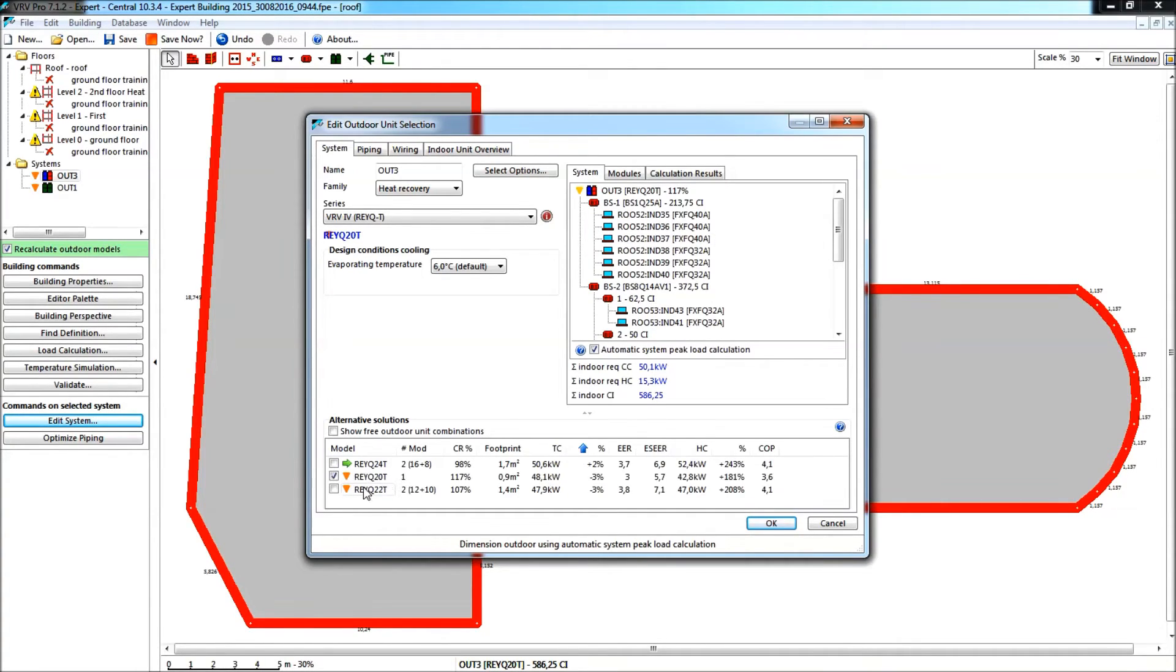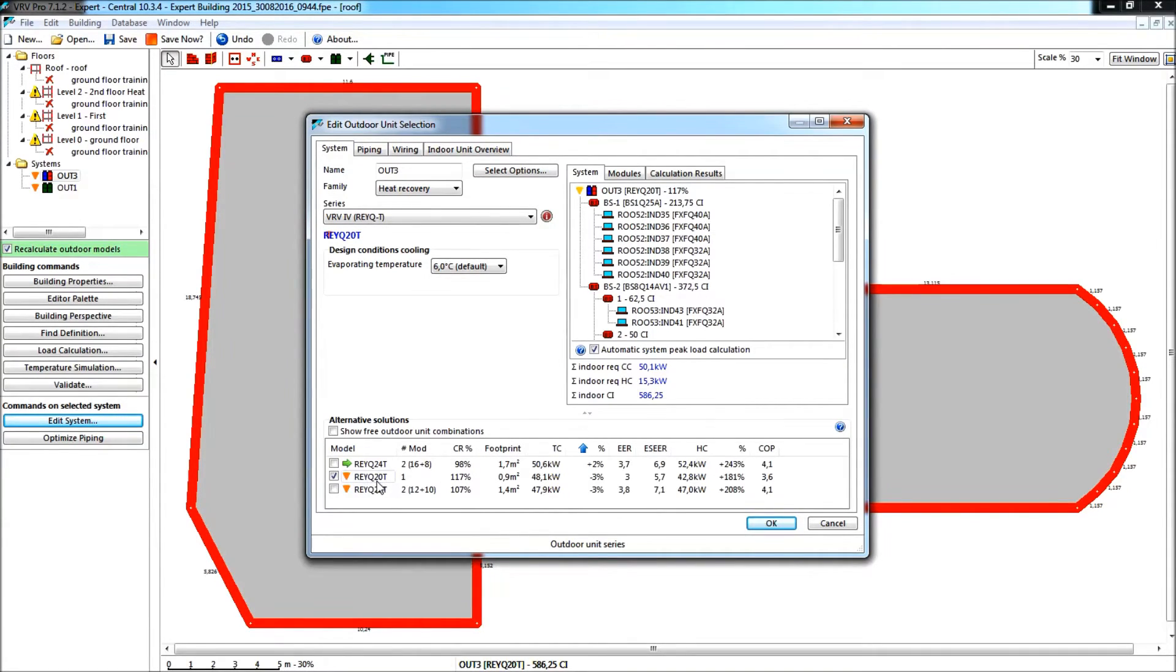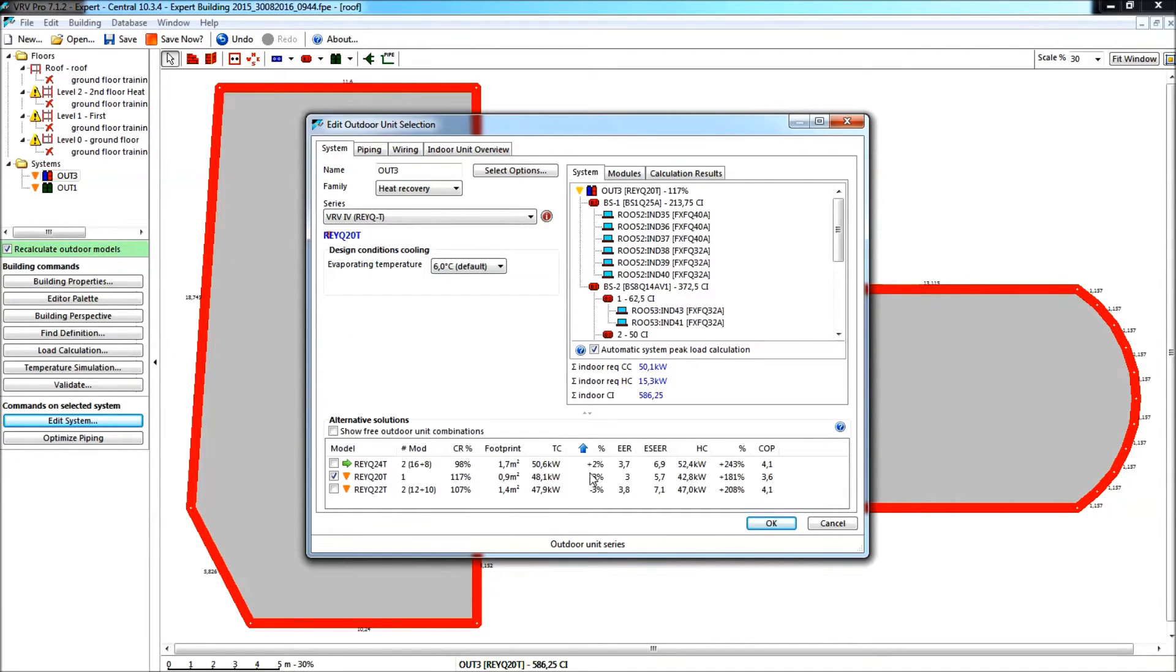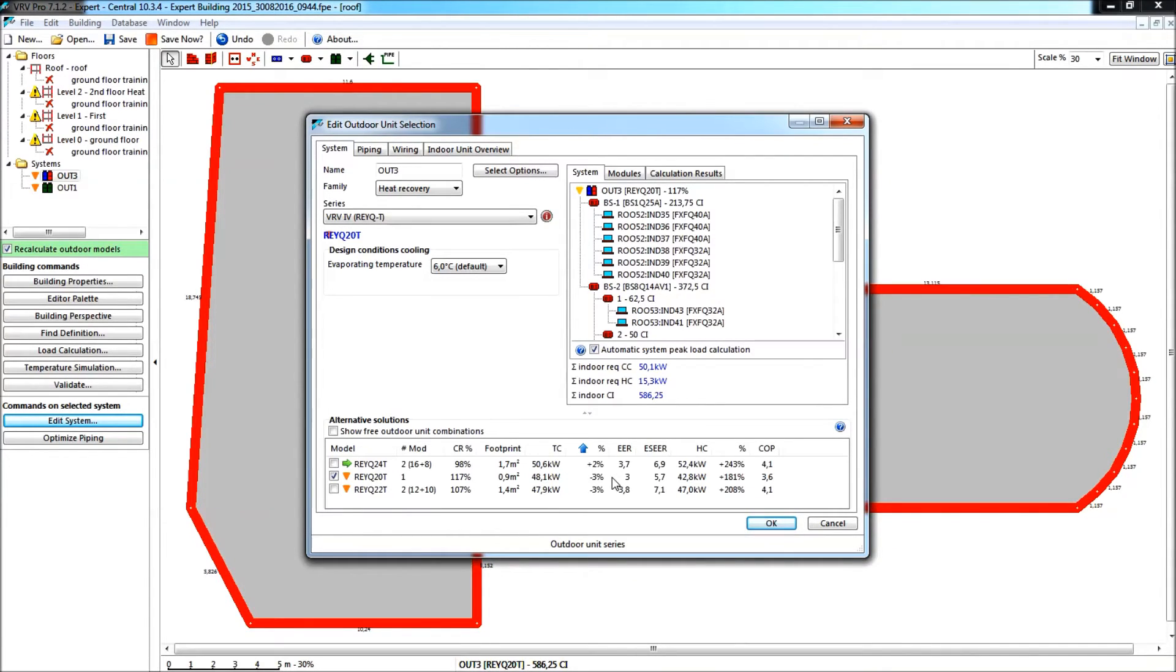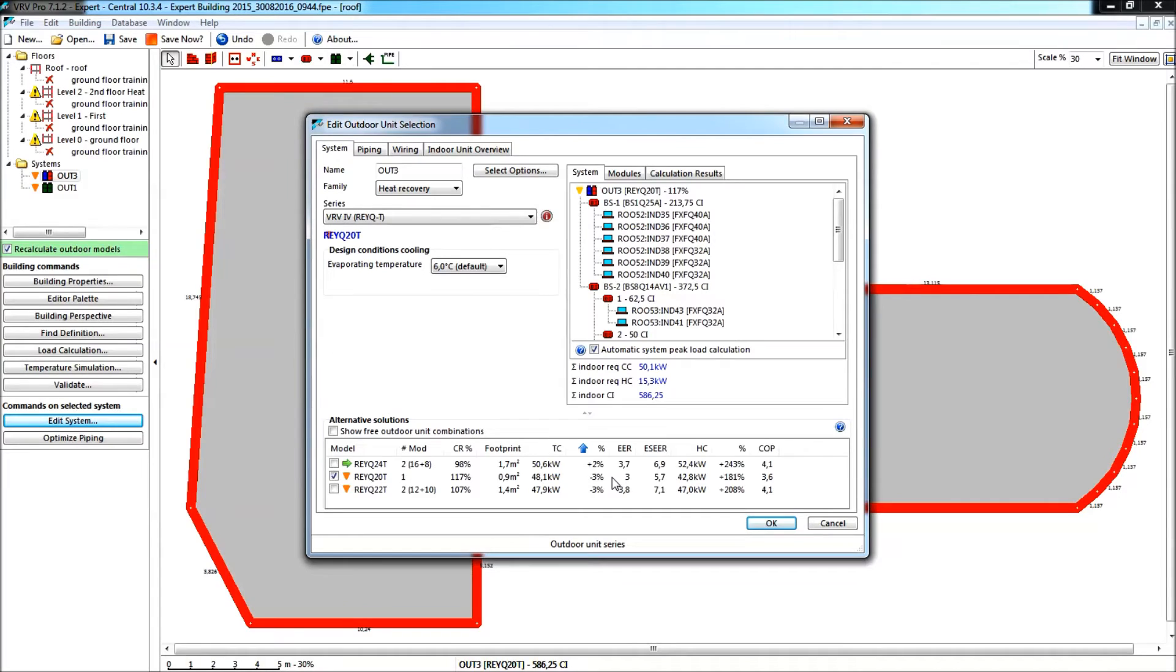And here again, I see that I did edit this system, and I preferred to have a higher connection ratio of 117%, so 20 horsepower, knowing that here, in doing so, instead of having excessive capacity, I have 3% shortage, but I can live with this, that during a couple of hours in a whole year, I will not manage to maintain the set point of 22 degrees, for instance, but that the room temperature would creep up to 22.5, so I am gladly to accept this.